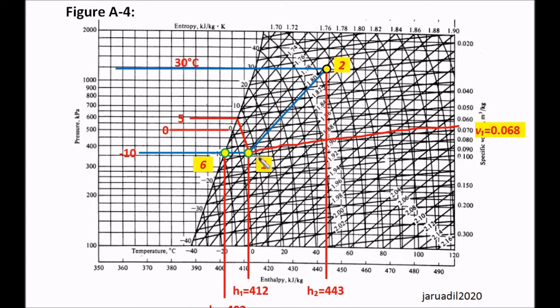Then from 1 to 2, you draw a constant entropy line. The constant entropy lines are the diagonal curves going upward. Draw the constant entropy line from point 1. Then, the condensing temperature of 30 degrees Celsius — locate 30 degrees, which is between 20 and 40 degrees. Wherever the constant entropy line crosses the 30 degrees Celsius line is point 2.